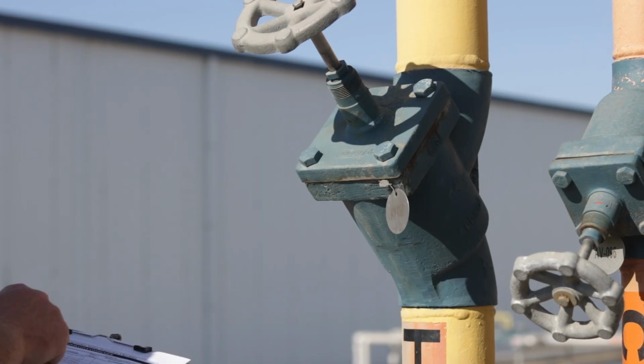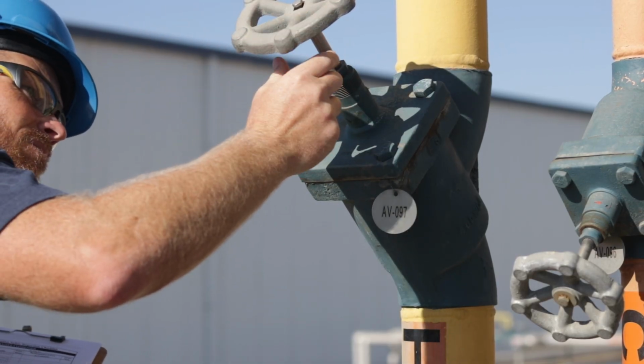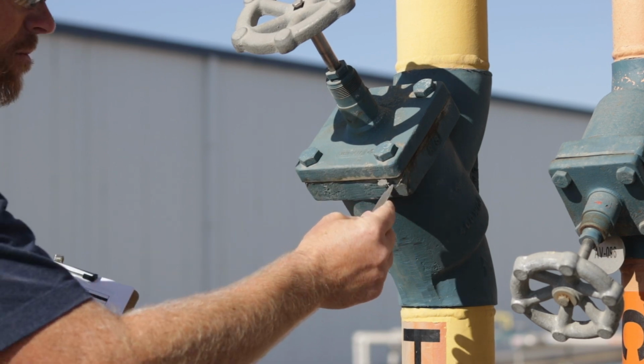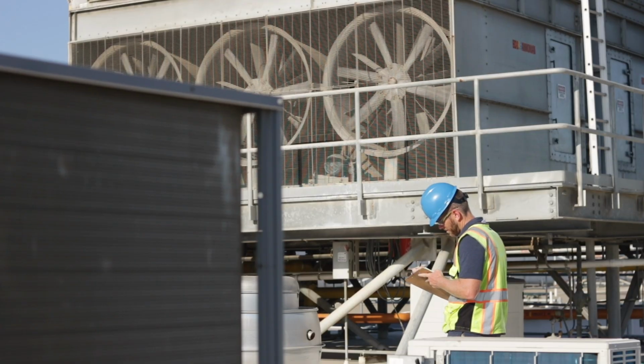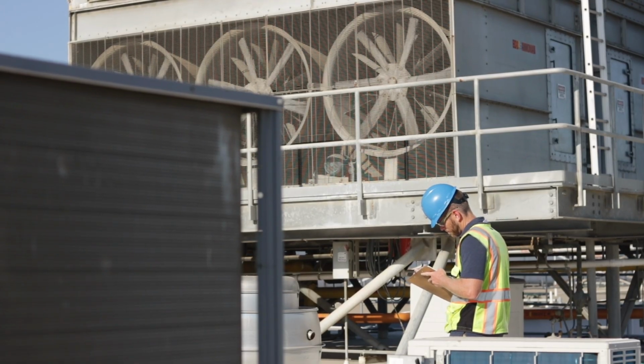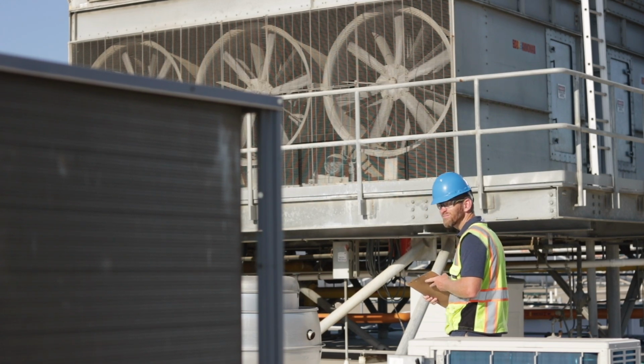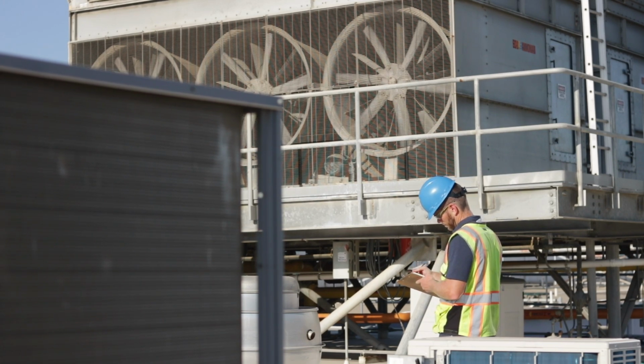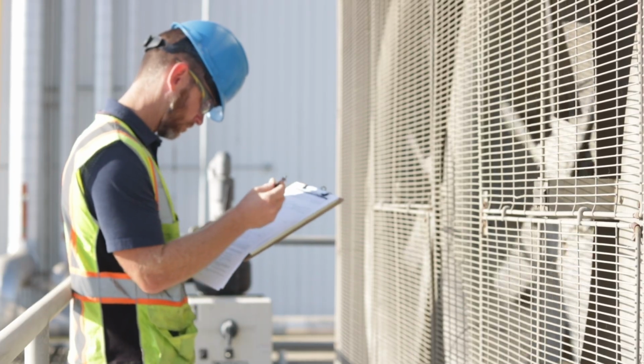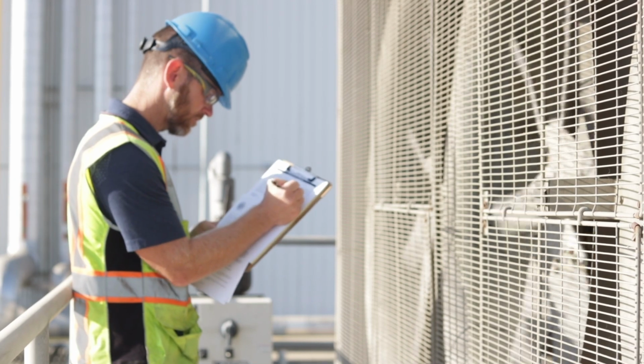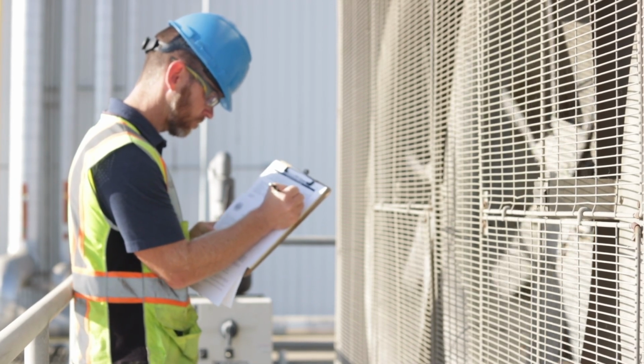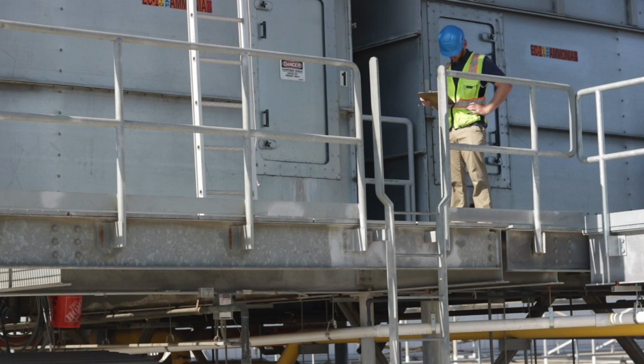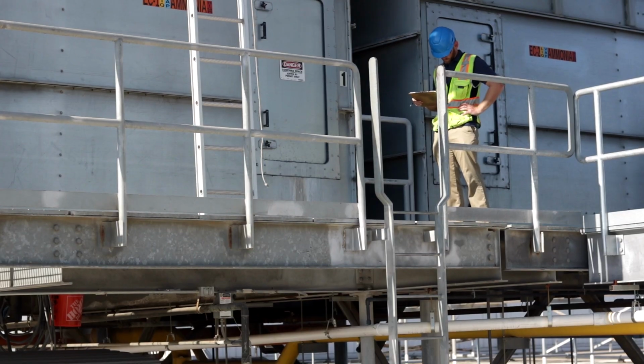Once it has been verified that the fans and pumps are running, the operator must ensure that all valves are in their proper positions. The inlet, outlet, and equalizer isolation valves must be open. If the system is equipped with an auto purger, the foul gas isolation valve will be opened as well. Once the evaporative condenser is running, it should be monitored by the operator for a period of time to ensure it is free from abnormal situations such as ammonia or water leaks.